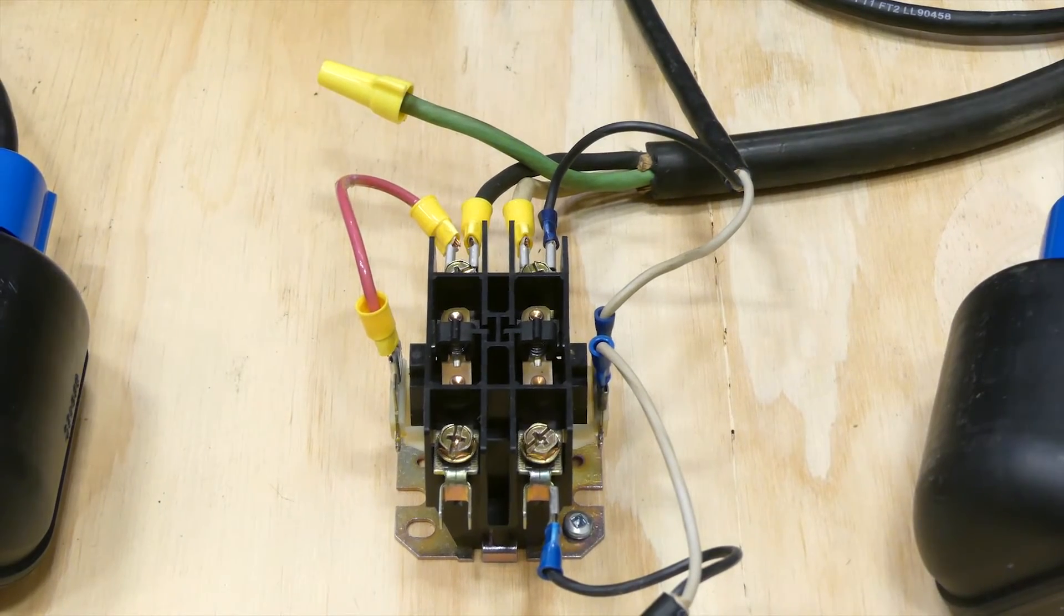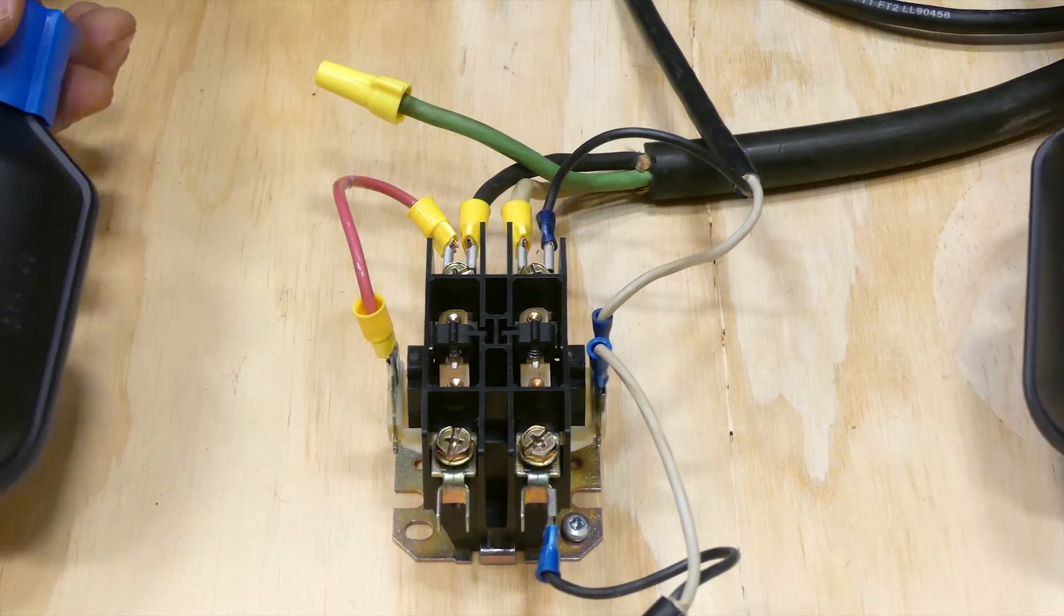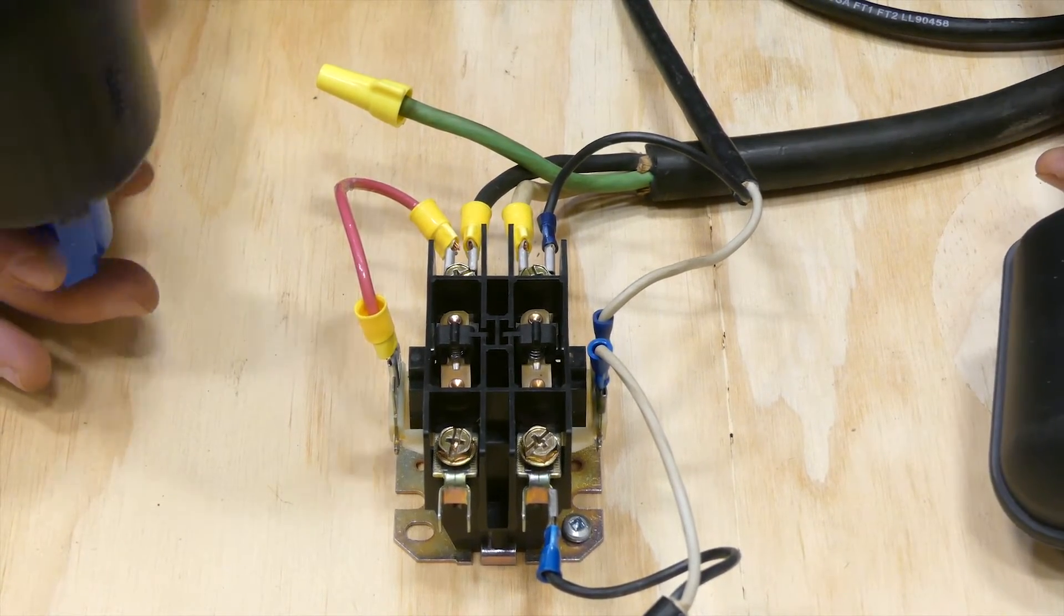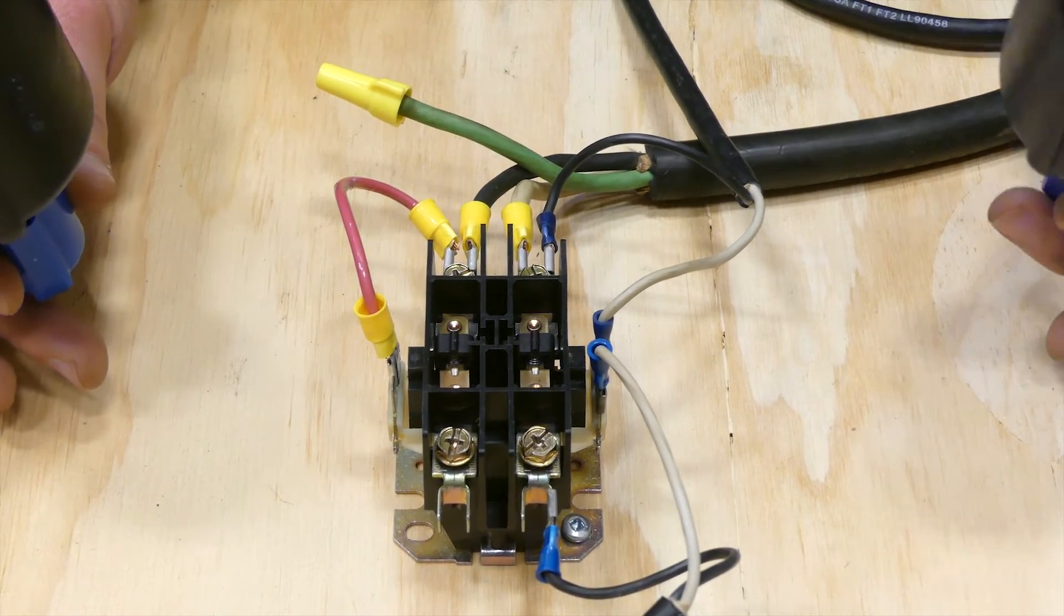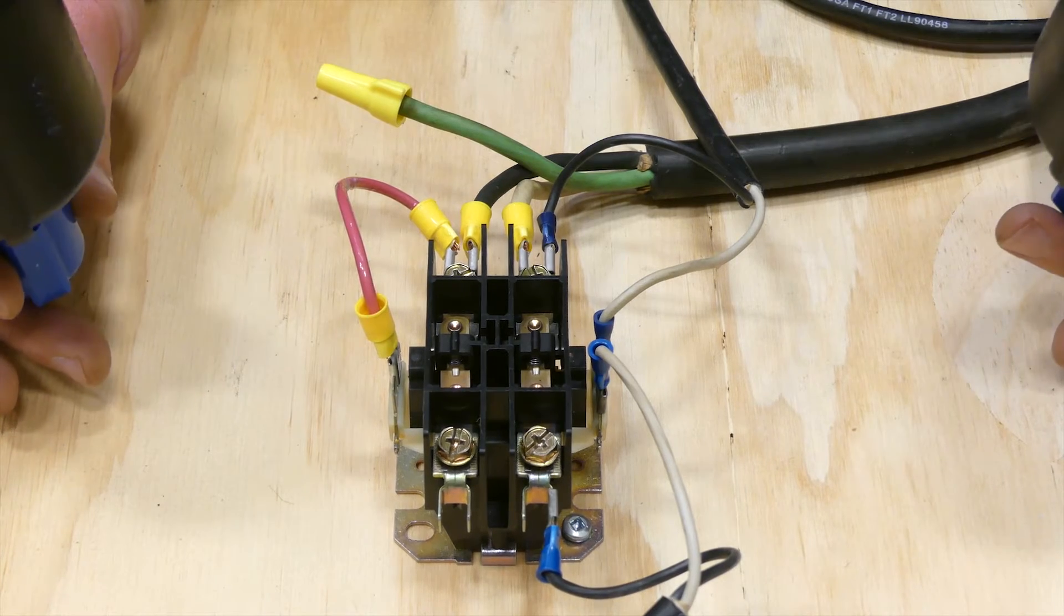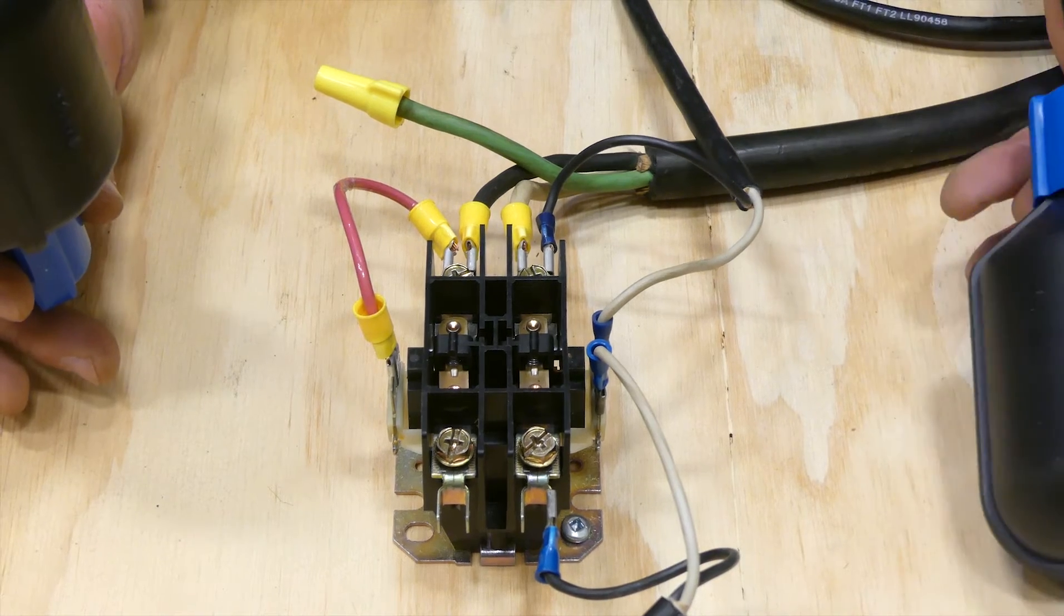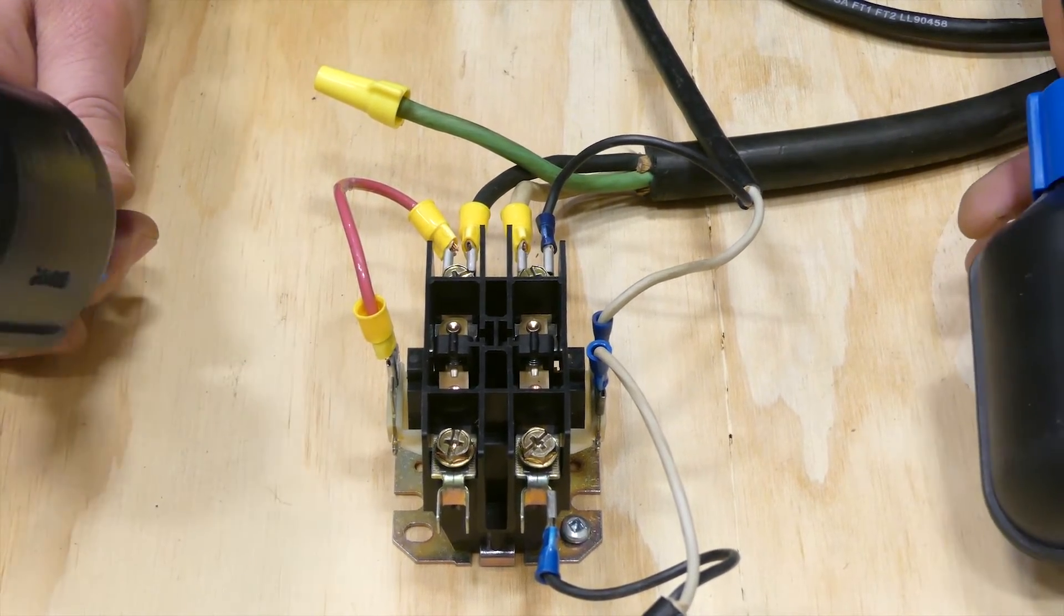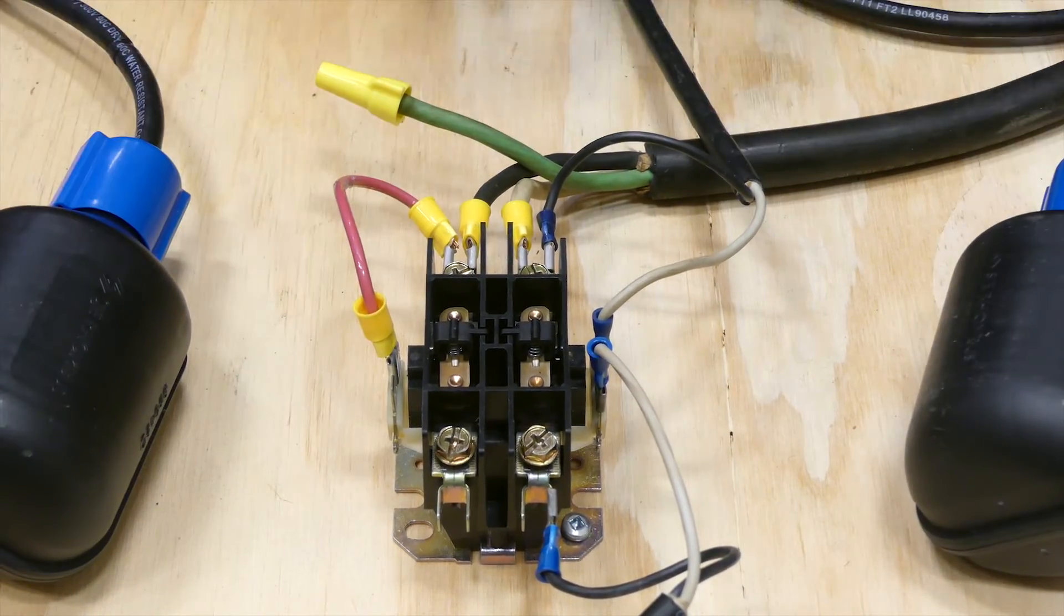Okay, so we've got our tank. The water level is—well, let's say the tank is pumped down. This float will be up, the water level continues to rise, then this float goes up, turns the pump system on. Finally, the water level starts to drop. This float switch shuts off, the pump continues to run until it reaches the float at the bottom of the tank and allows the system to shut off. As simple as that.